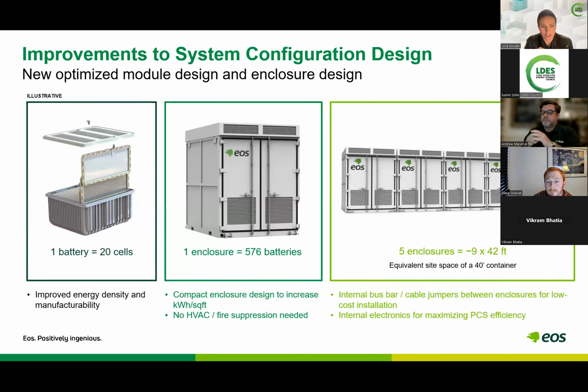We get asked this a lot: the 5 enclosures are 1 container. What's your capacity here, is this megawatts, is this kilowatt hours? Yeah, it's megawatt hours, we're always an energy battery, built for energy. These are our conceptual designs, and we're working through different iterations of arranging the cabinets, but the current one is about 3 megawatt hours in that space. So we're able to dramatically improve our energy density too, to your point.